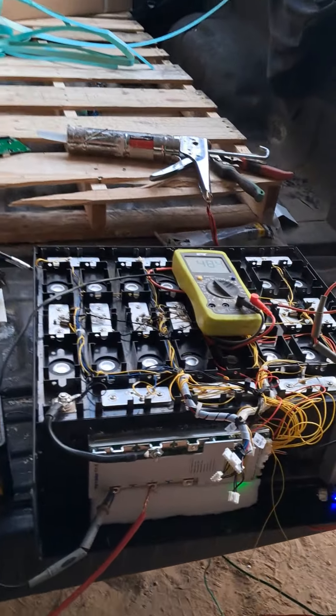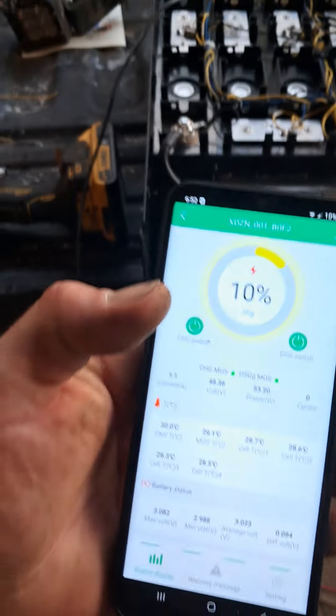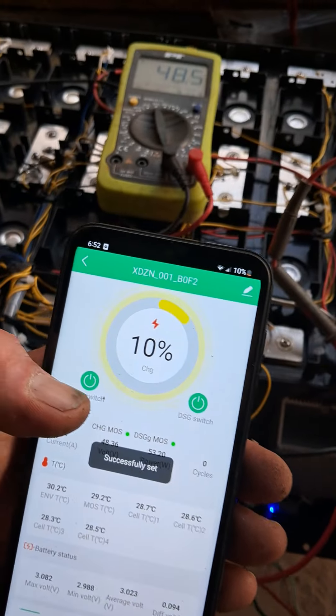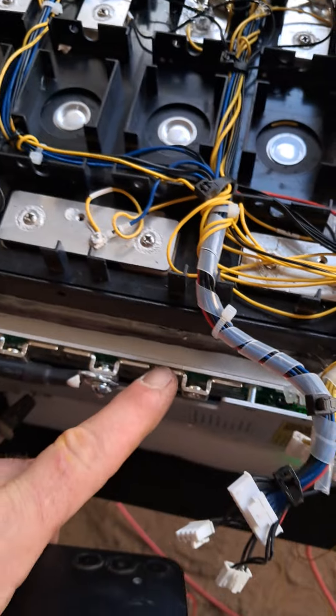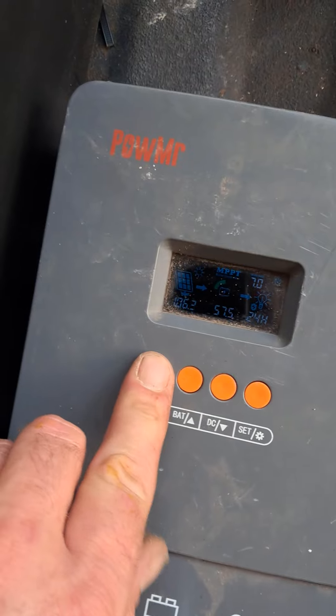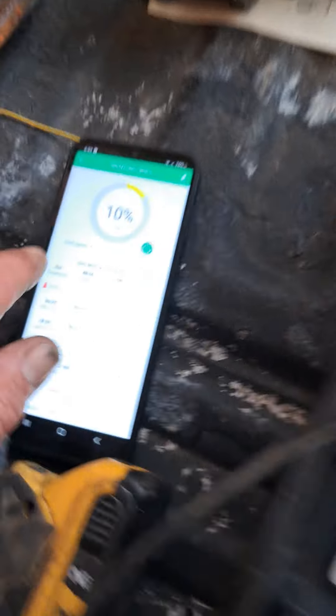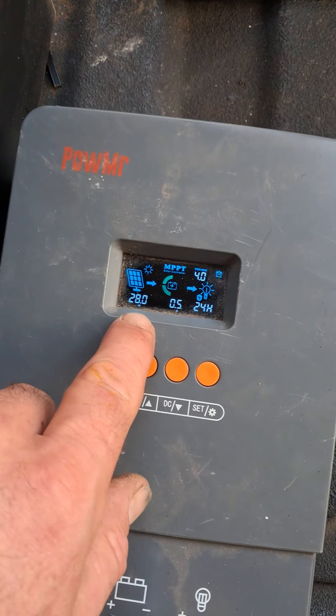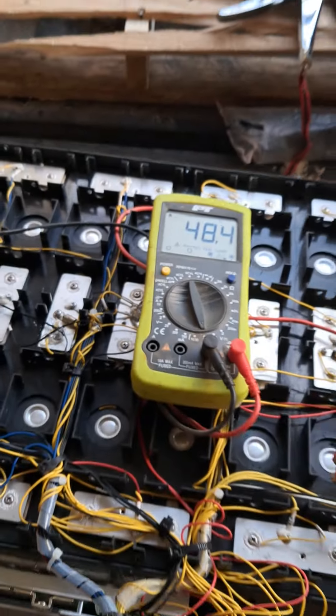Wrapping up this install on the battery — the BMS is now communicating with the system, so we're able to charge and discharge pretty much anytime. Right now we just stopped charge mode, so it shows an open circuit and won't accept any charge coming in, showing zero watts. I'll go ahead and turn the charge circuit back on — it stabilizes back to 48.4 volts and is climbing, slamming in roughly about 315 watts. Looks like a good test so far.